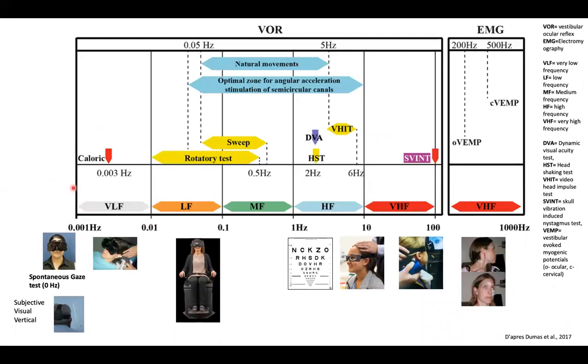The calorics are at 0.003 Hz and the spontaneous gaze at 0 Hz. Other tests like the rotary chair provide information about low and medium frequency. The video head impulse test provides information between 3 and 6 Hz. We can do dynamic visual acuity and head shaking tests around 2 Hz approximately. The skull vibration-induced nystagmus test is at a very high frequency, around 100 Hz. VEMPs can be done at 200 and 500 Hz.